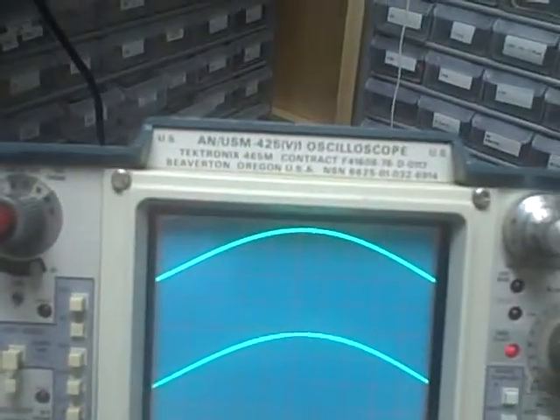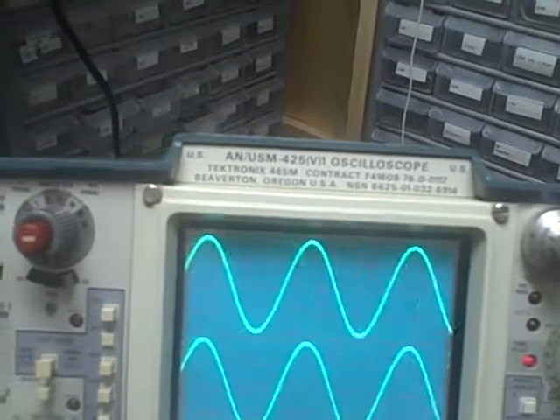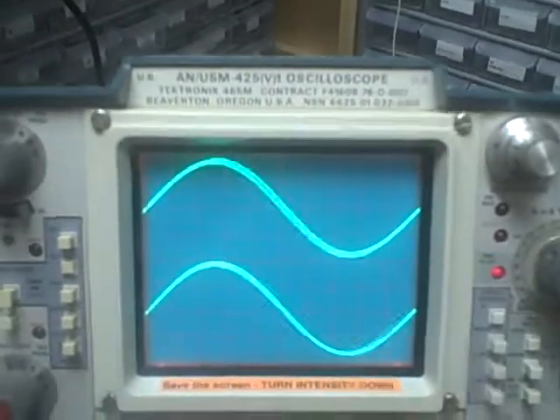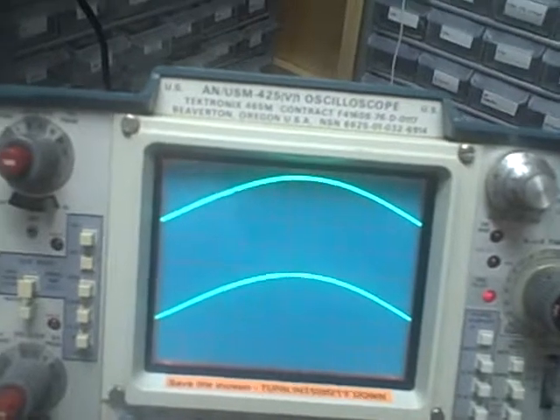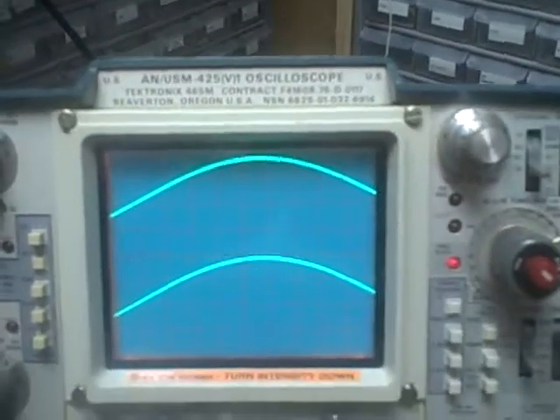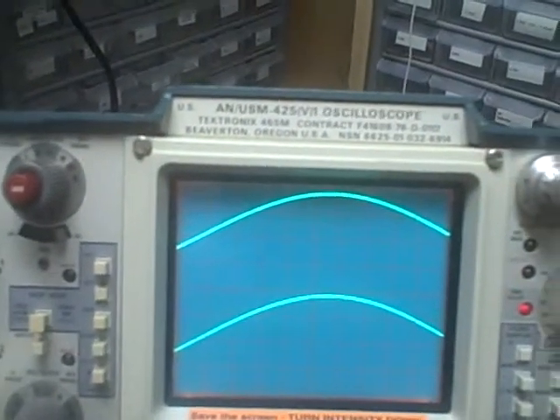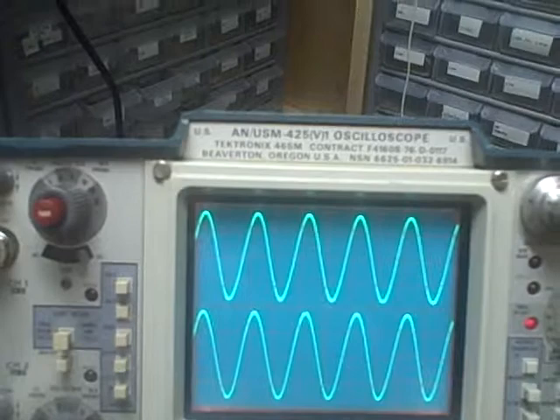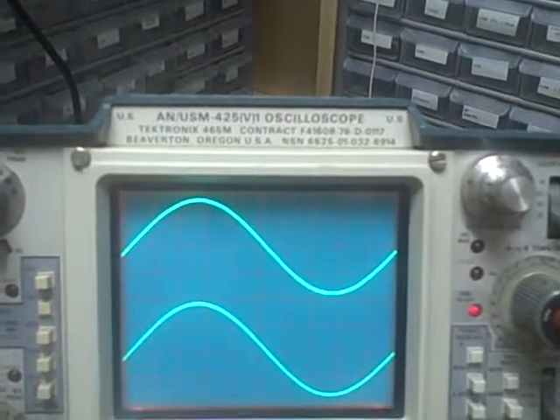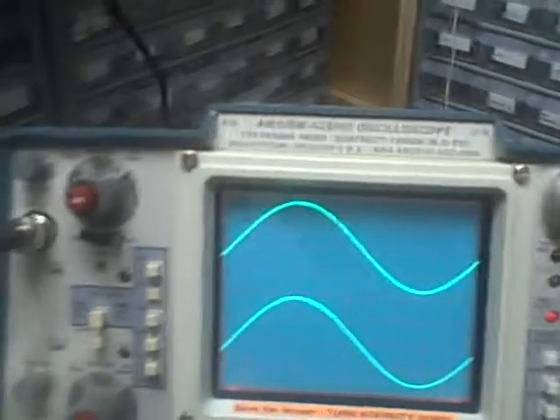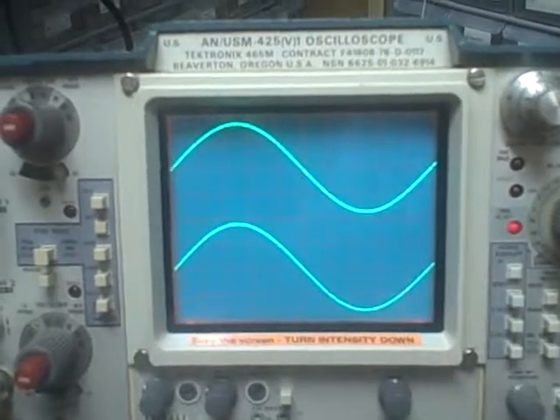5 microseconds — we should be good to 20 kilohertz. Right on the money. 2 microseconds — we're good to 50 kilohertz. 1 microsecond — should be good to 100 kilohertz. 0.5 microseconds — should be good to 200 kilohertz. 0.2 microseconds — we should be good to 500 kilohertz. Right on the money.